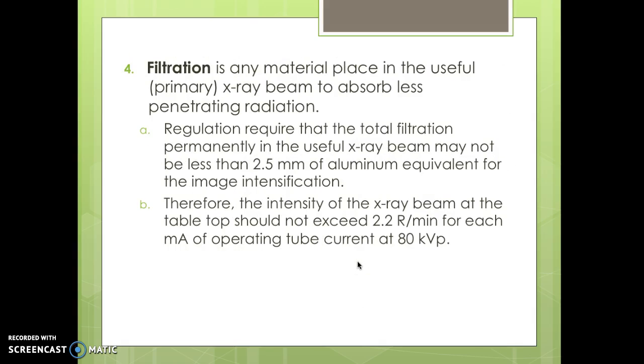Filtration: any material placed in the useful primary x-ray beam to absorb less penetrating radiation. Regulations require that the total filtration permanently in the useful x-ray beam not be less than 2.5 millimeters of aluminum equivalent. For image intensification, the intensity of the x-ray beam at the tabletop should not exceed 2.2 R per minute for each mA of operating tube current at 80 kVp.